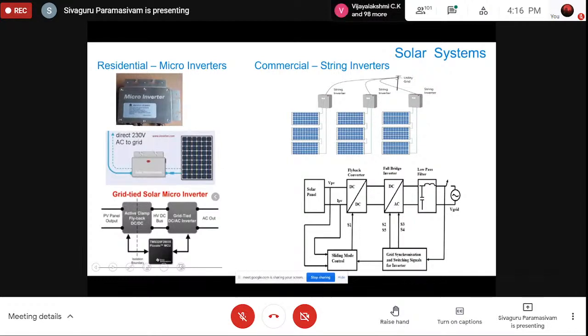Okay, and then you can see a grid synchronization block, which means from the grid we need to tap a feedback. Whatever the voltage, frequency, phase angle, and power factor is at the grid side, the inverter should also respect that, and it should be connecting to the grid with the same frequency, voltage, and phase angle. Otherwise the system will not work. Otherwise the system will trip. So that's the reason we take a feedback from the grid, and then we control the power electronic switching with respect to the feedback we receive from the grid.